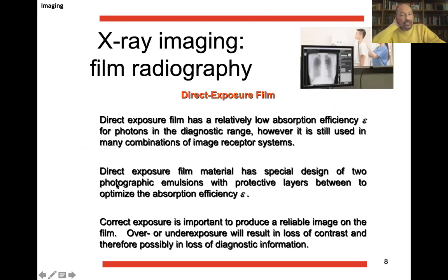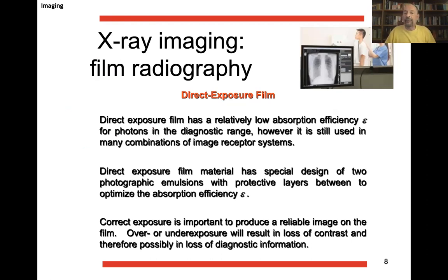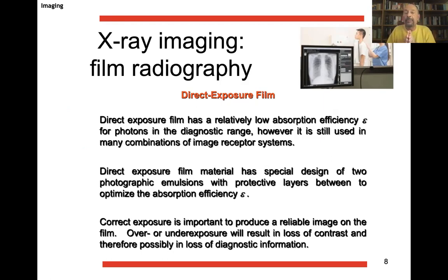X-ray imaging — so-called film radiography — is still extremely popular. Traditionally done with films, you actually expose film and still do so many times, holding the cassette with the film inside. The direct exposure film has a relatively low absorption coefficient epsilon for photons in the diagnostic range. They have a special design of two photographic emulsions with protective layers in between to optimize the absorption coefficient. Correct exposure is important; over- or underexposure results in loss of contrast and possibly loss of diagnostic information.